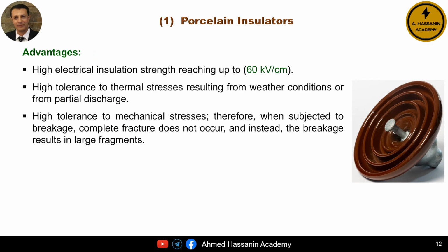They have a high electrical insulation strength, provided that the insulator is pure and free from any pores, impurities, or air bubbles during manufacturing. The dielectric strength or electric field intensity of these insulators is approximately 60 kilovolts per centimeter. Porcelain insulators can withstand thermal stresses caused by various weather conditions as well as thermal stresses resulting from partial discharge to a large extent. It can also be observed that porcelain insulators can endure high mechanical stresses.